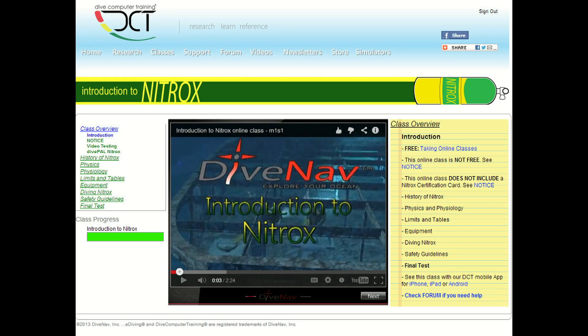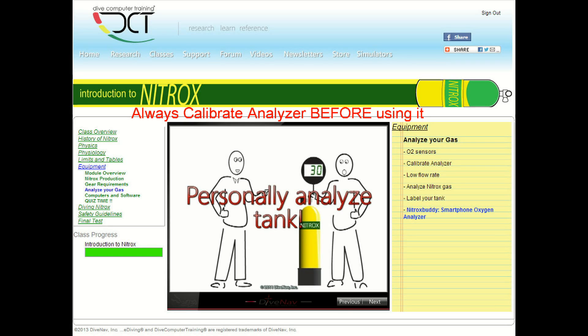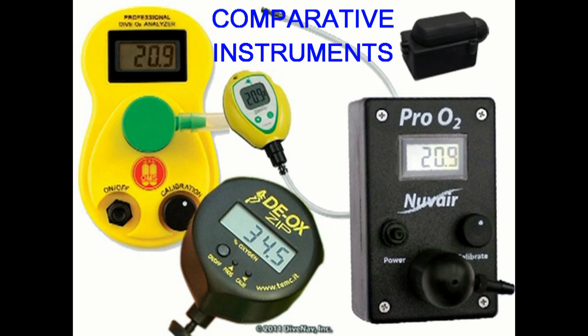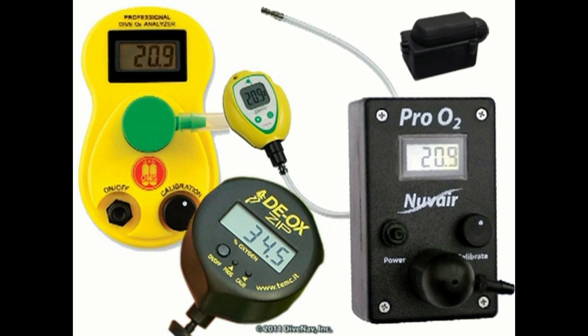When you took your nitrox class, you learned that you must always calibrate an oxygen analyzer before using it. This is because oxygen analyzers are comparative instruments and not absolute instruments.